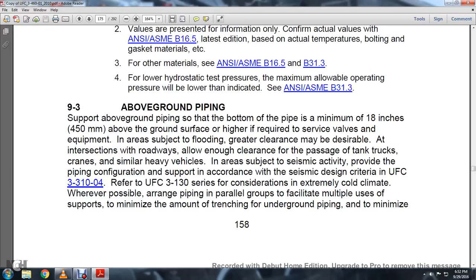For consideration of extremely cold climates, wherever possible, arrange piping in parallel groups to facilitate multiple use of the supports, minimize the amount of trenching and underground piping, and minimize the number of pipe styles needed. Consider constructability, maintenance, and spacing of the piping, and generally use the following rule of thumb.